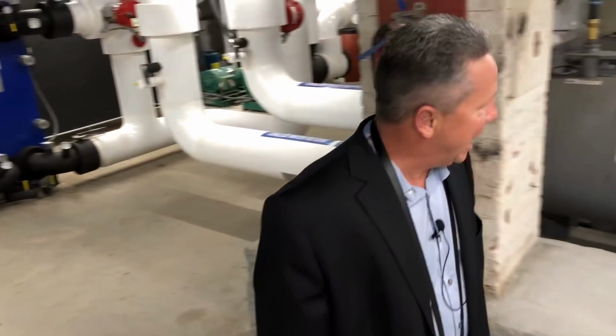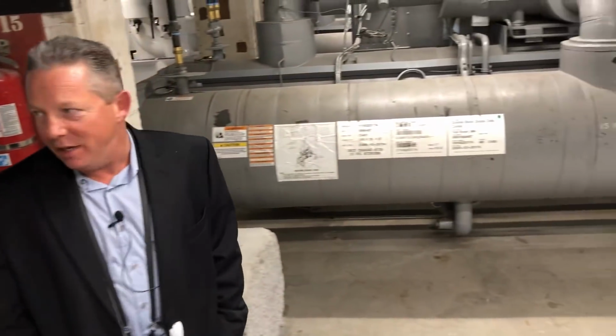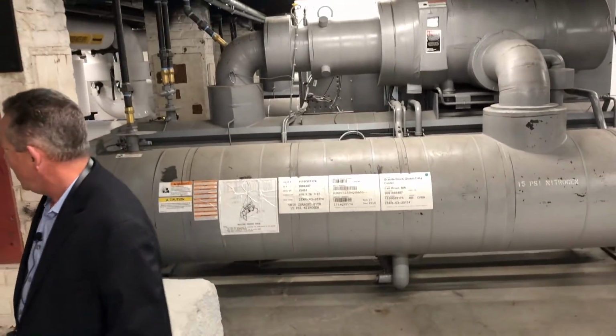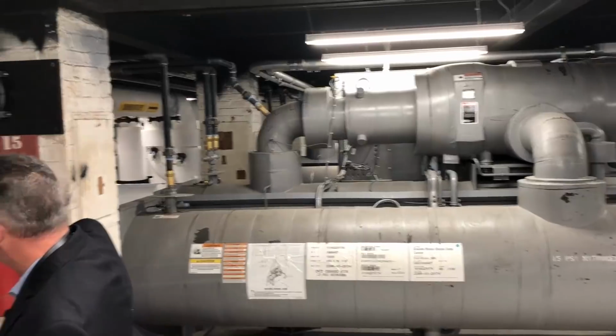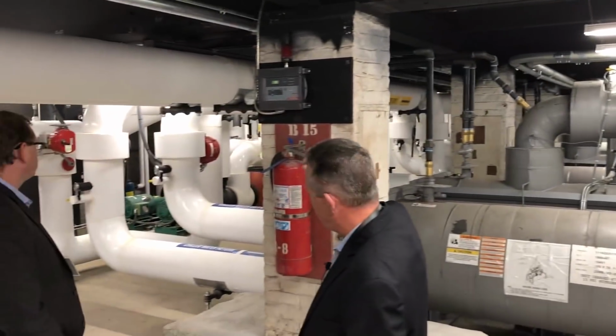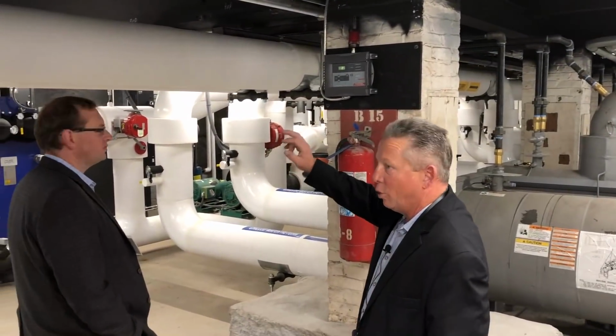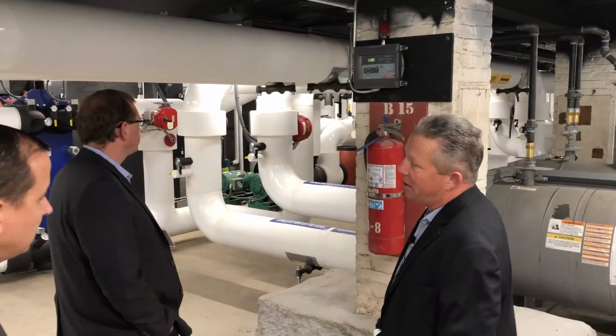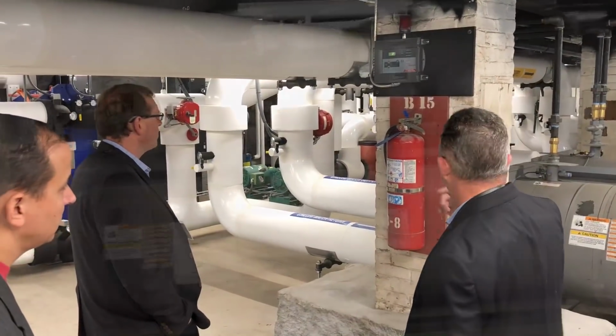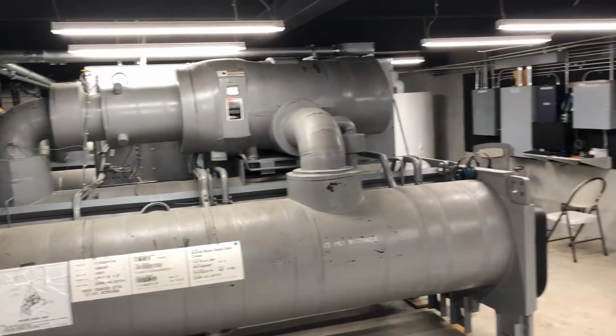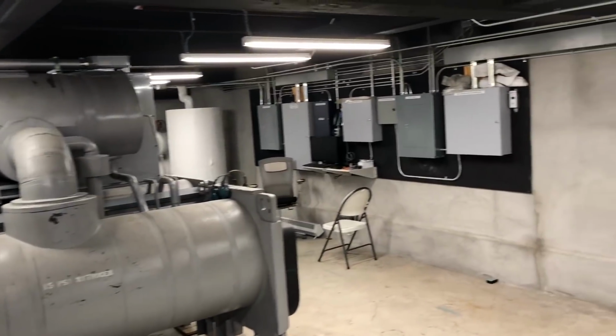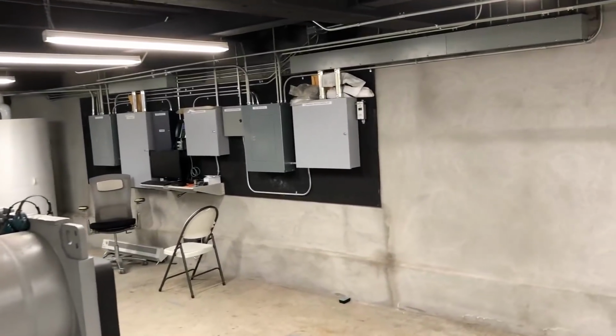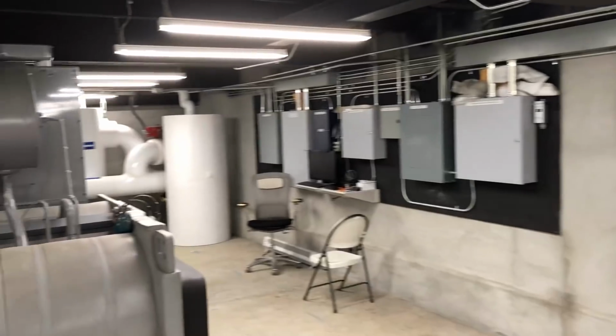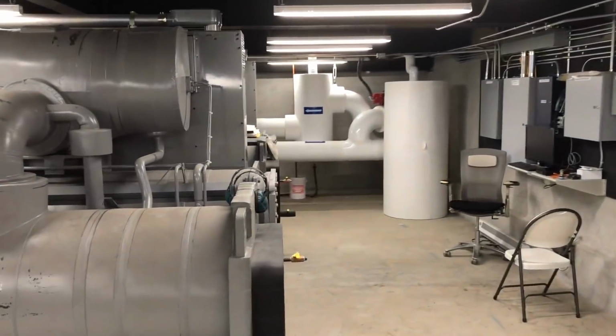Yeah, so this is dual 300-ton Carrier screw chillers, best in breed, highly efficient. They have dual pumps for the chilled water loop, dual pumps for the cooling tower loop, dual cooling towers, plate and frame heat exchanger. We just got about $385,000 worth of electrical rebates because of how efficient the design is. If it was below 50 today, we'd be running on free cooling. You wouldn't even hear the chillers running.